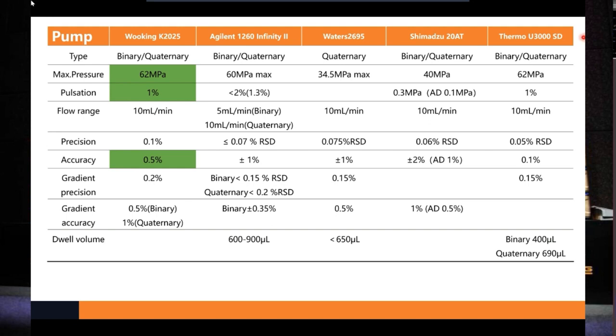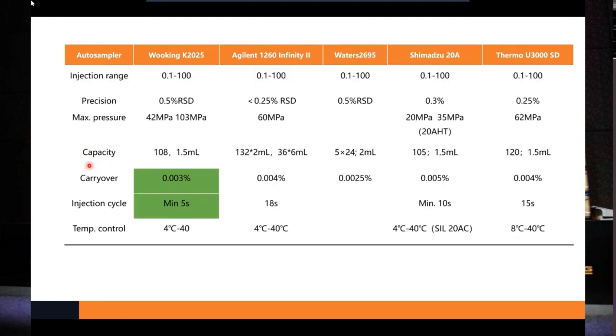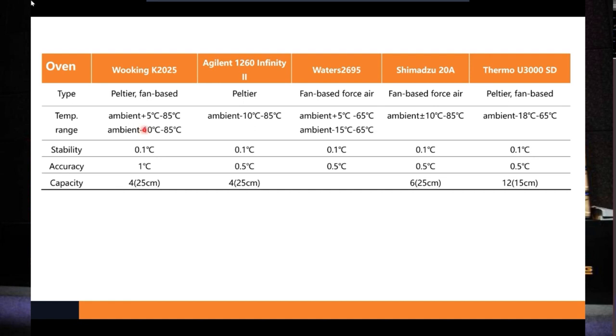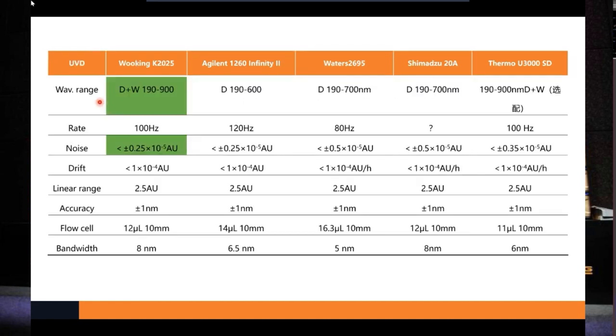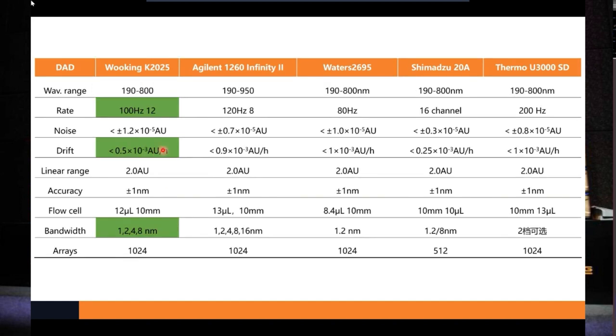1260. For the pump, K2025 has some advantages on maximum pressure, pulsation, and flow accuracy. And for the sampler, the carryover and injection cycle time is better compared to others. And for column oven, the specs are pretty similar. And for UV detector, K2025 has a wider wavelength range because we use 2 light sources, and the noise is controlled at a very good level. For DAD, specs are pretty similar.